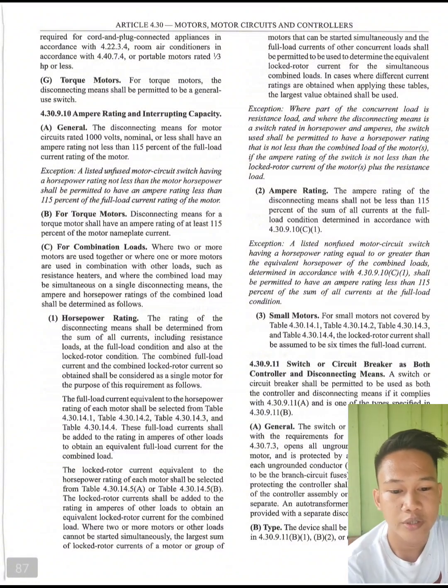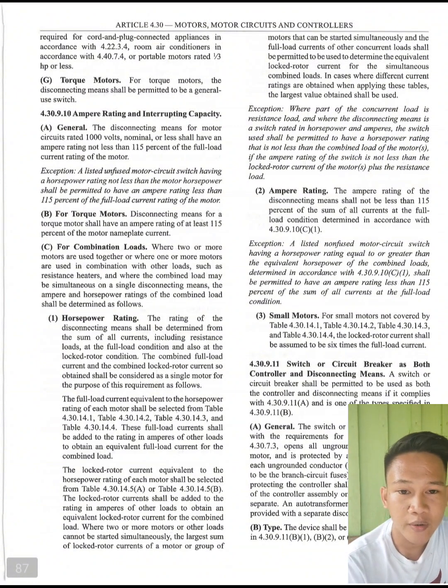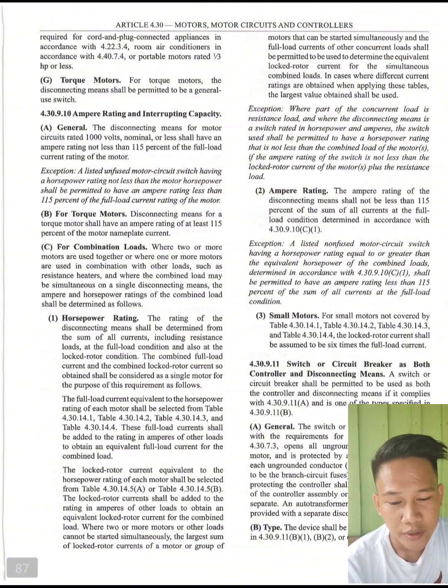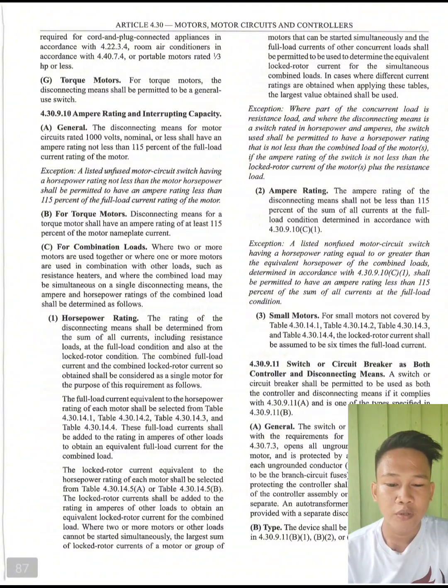Next is for combined loads, where two or more motors are used together or where one or more motors are used in combination with other loads, such as resistance heaters, and where the combined load may be simultaneous on a single disconnecting means. The ampere and horsepower ratings of the combined load shall be determined as follows. So first, we have horsepower rating. The rating of the disconnecting means shall be determined from the sum of all currents, including resistance loads, at the full-load condition and also at the locked-rotor condition. The combination of full-load current and the combination locked-rotor current so obtained shall be considered as a single motor for the purpose of these requirements as follows.